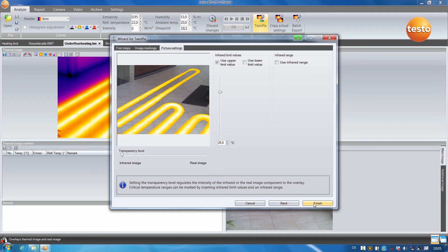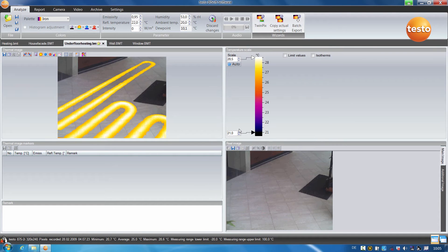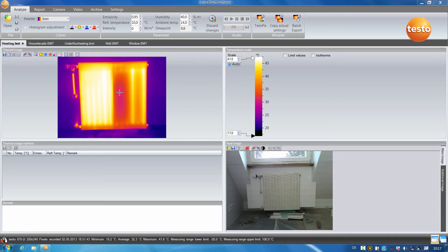I finished the image and have now guaranteed that the underfloor heating will not be damaged in the case of any constructional changes. The hot and cold spot recognition and the previously mentioned Profile Line assist me when testing radiators for weak spots.